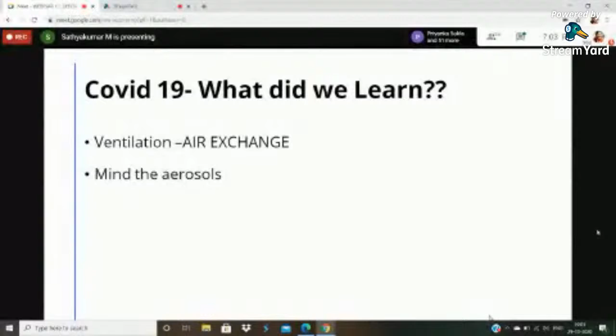When I say air disinfection or clearing, how do we do it? One is that we have to provide adequate ventilation such that the airflow clears the contaminated aerosols from the dental operatory, which can be reasonably achieved within a minimum of 6 air changes per hour. When I say 6 air changes, every 10 minutes there's one set of new air which is made, mainly achieved by HEPA filters, the high efficiency particulate air purifiers.